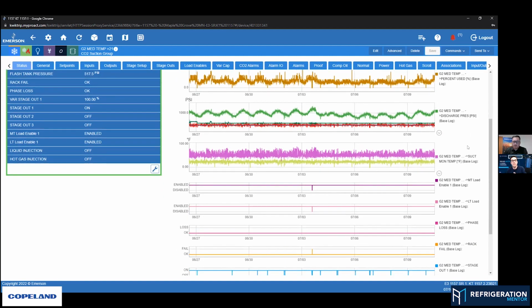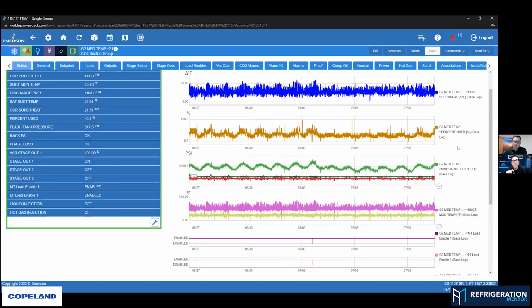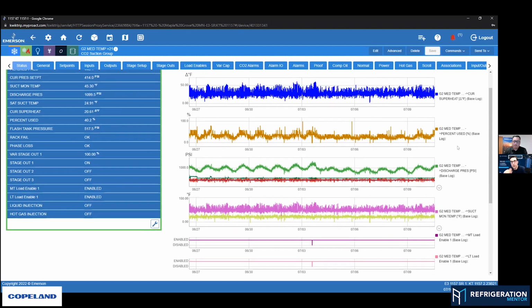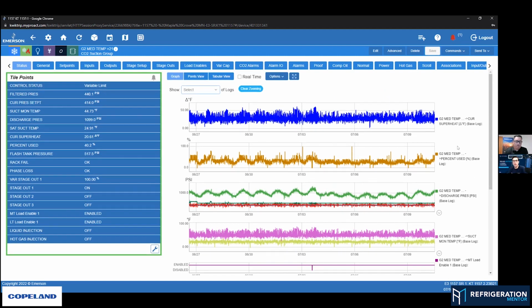So what would be some examples? Oh, there's a lot there. What would be some of the graphs you'd look at when helping out a contractor, since you like a lot of information? Would it be these ones here, or specific ones you'd look at right away? Typically it's the suction pressure, discharge pressure, the high pressure valve and where it's positioned, the bypass valve as well, and then what the gas cooler is doing.